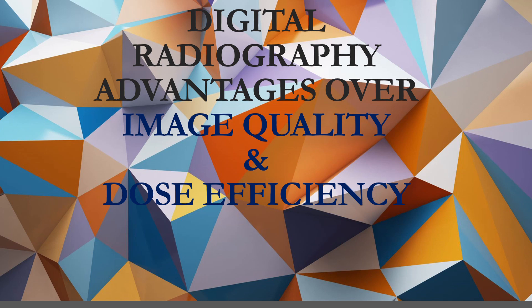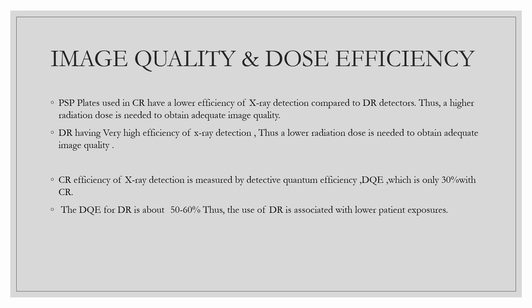Our next topic is image quality and dose efficiency — how digital radiography has more advantages over CR in this area. The PSP plate used in CR has a lower efficiency of X-ray detection compared to DR detectors. Therefore, a higher radiation dose is needed to obtain adequate image quality in CR, whereas DR has very high efficiency, requiring a lower radiation dose.